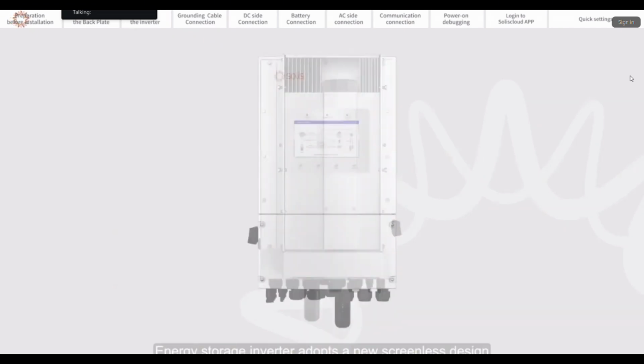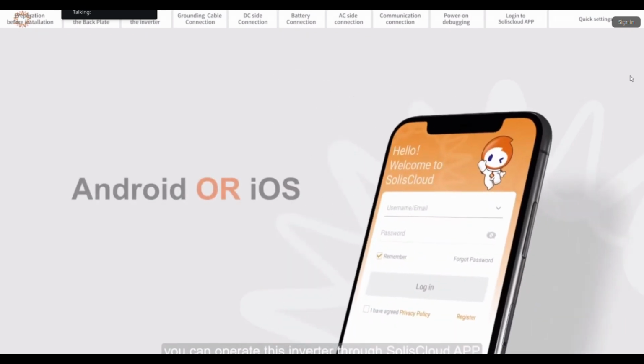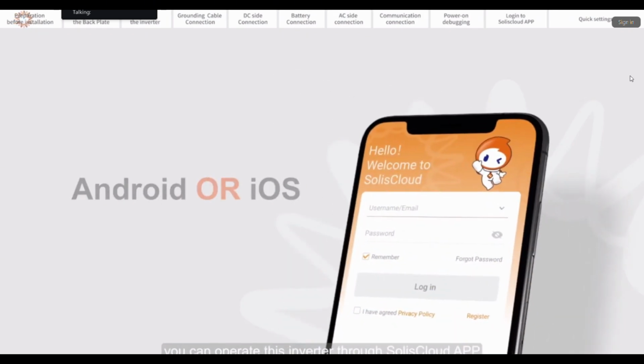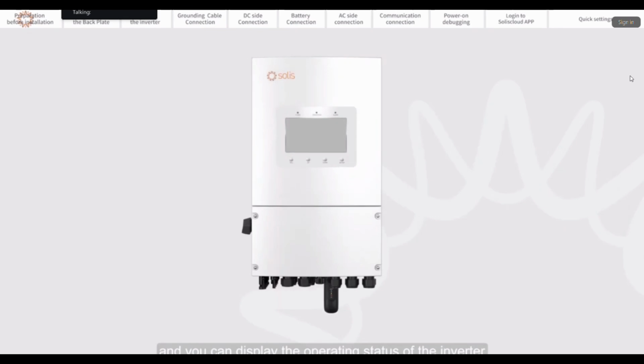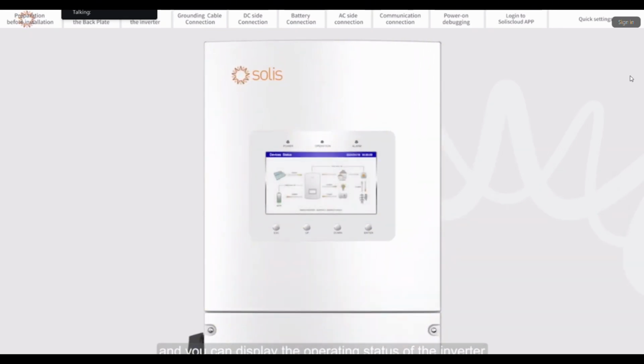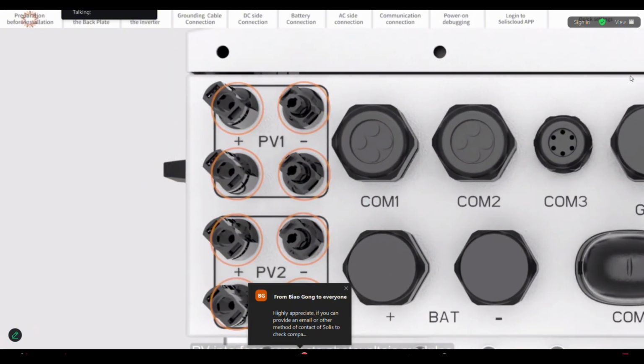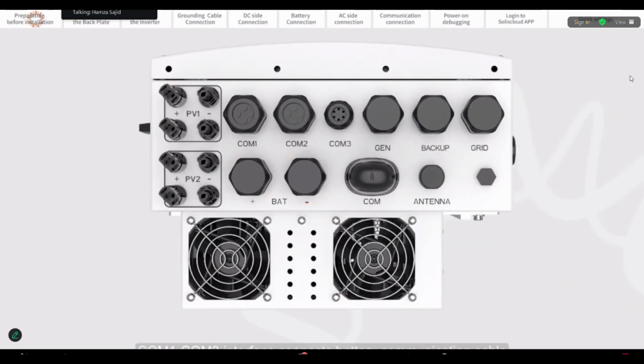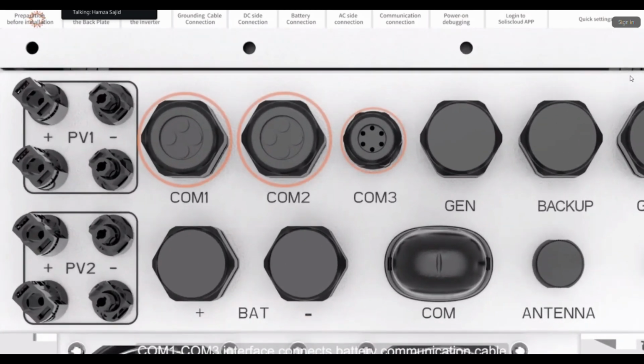Energy storage inverter adopts a new screenless design, and you can operate the inverter through the Solis Cloud app. And you can display the operating status of the inverter through the light bar on the inverter. The PV interface connects photovoltaic modules. Input photovoltaic energy into the system. BAT plus and BAT minus interface the battery. COM1 to COM3 interface connects the battery communication cable, the CT wire, the parallel cable.